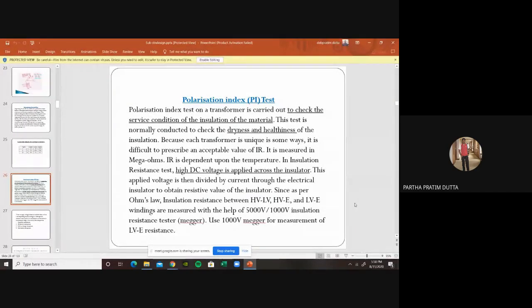So the insulation resistance result we get in mega ohms for 10 minutes and for 1 minute, we divide, and it should always be greater than 1. That means the mega result of the insulation for the 10-minute test using the 5000 volt Megger, divided by the mega result for the 1-minute test, should always be greater than 1, then the polarization index is correct. And this should be done for the HV system, LV system, HV to E and LV to E. That is the polarization index we usually do.